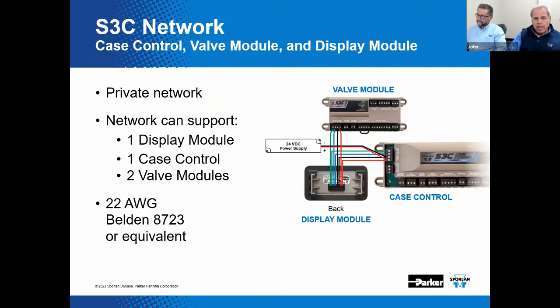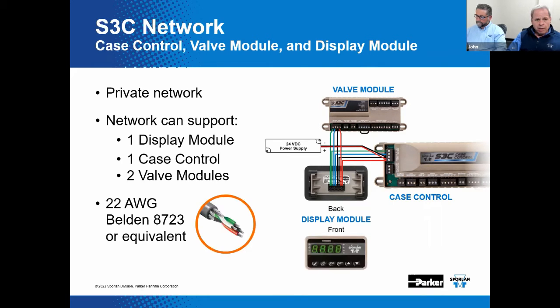And what do we have here? We've got a slide that details the wiring of the network and shows how the different devices are linked together. Note here that we've also shown both the front and back of the display module, and we're just showing the network of the valve module, the case control, and the power supply. This network can support one display module, one case control, and up to 2 valve modules.